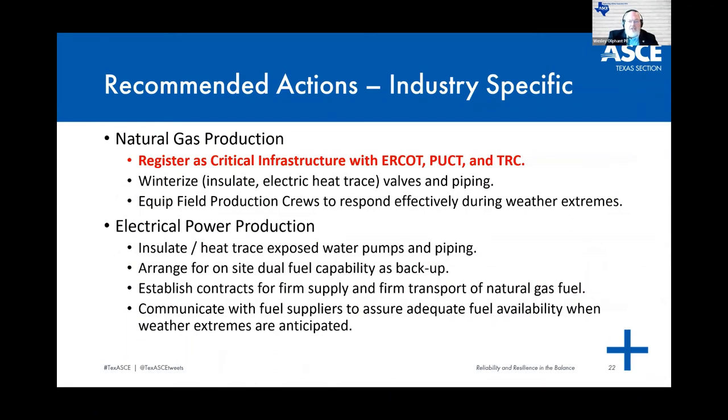And finally, industry-specific recommendations on the natural gas side are: winterize. Register as critical infrastructure with ERCOT, PUC, and TRC, and develop the contingency plans needed for field crews to respond effectively during extreme weather events. On the electricity side, same thing with generators, winterize. Add dual fuel source capability as backup if possible. Establish firm supply and firm transport of natural gas needed to effectively operate, and improve communications with fuel suppliers in advance to adequately ensure capacity when these types of events are forecast.